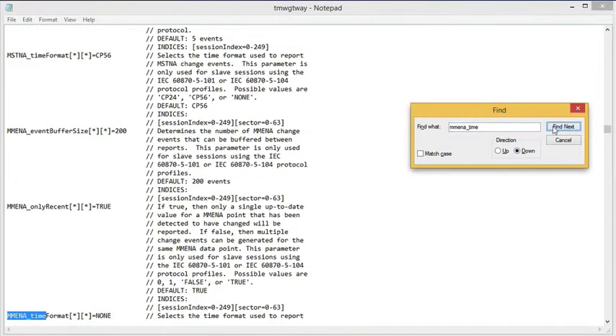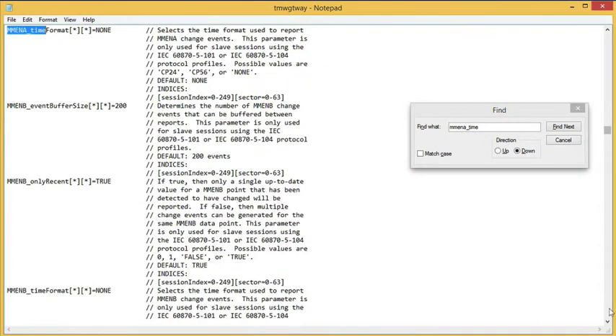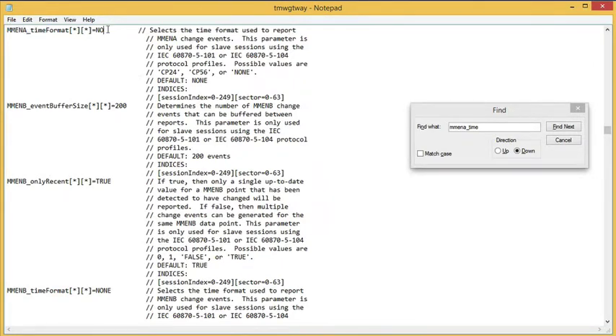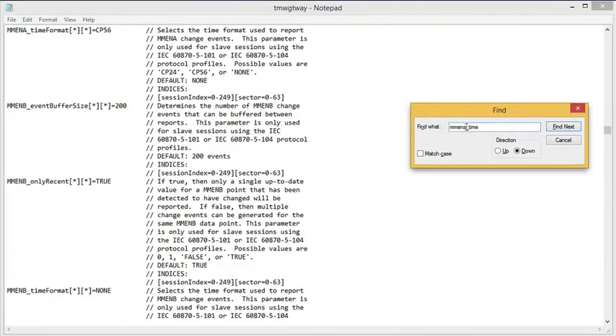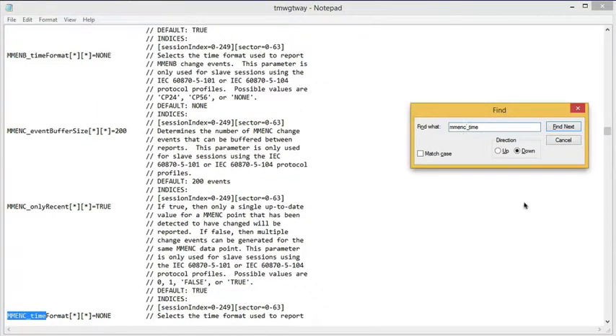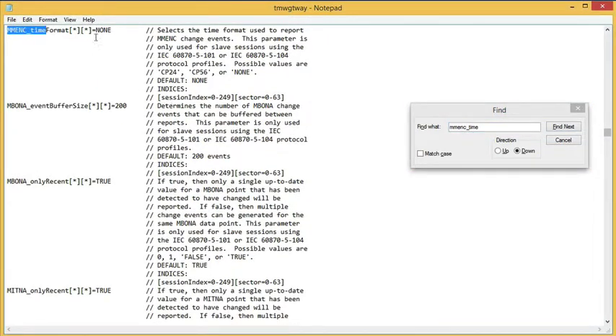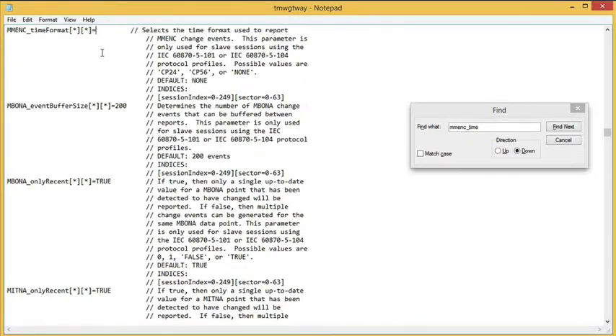Now I'm going to look for my measurands. Here's my normalized measurand. Notice that it defaults to no timestamp. So I'm going to change that to be a CP56. And then finally look for my float measurand. And again, it defaults to no timestamp, and I'm going to change that to a CP56.